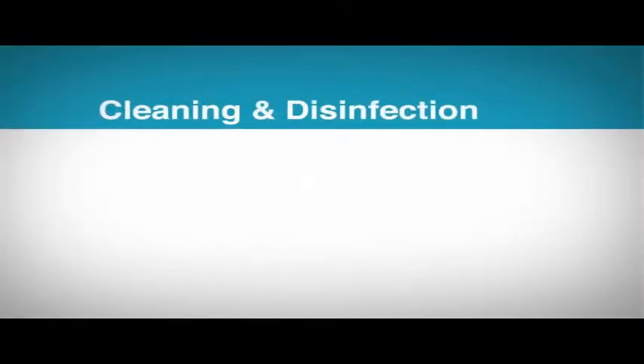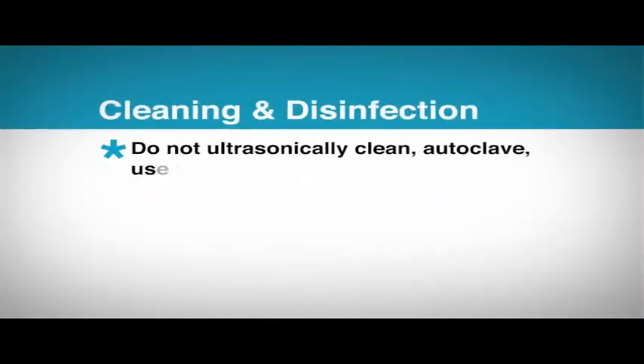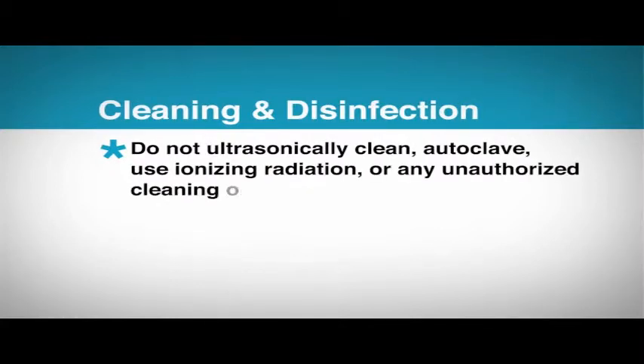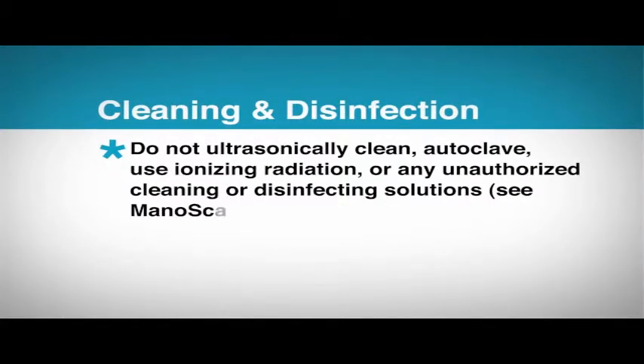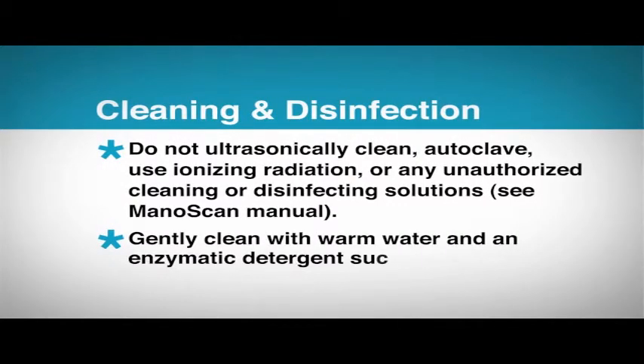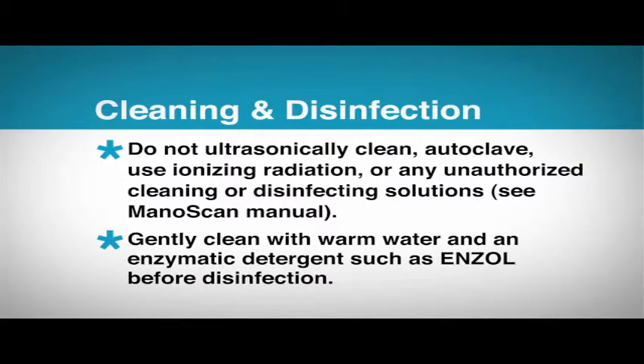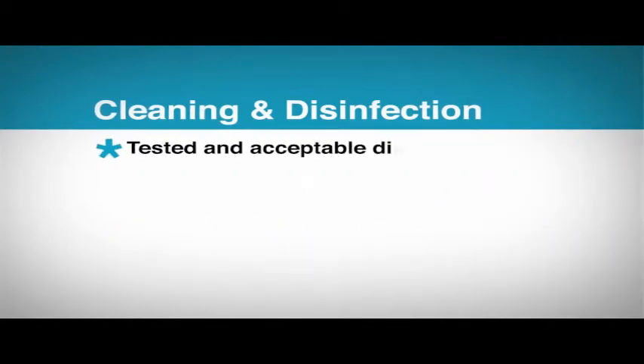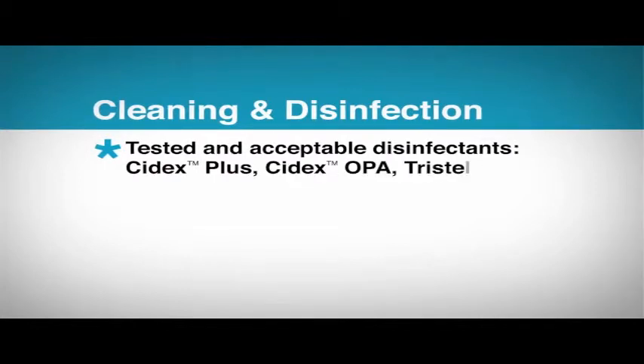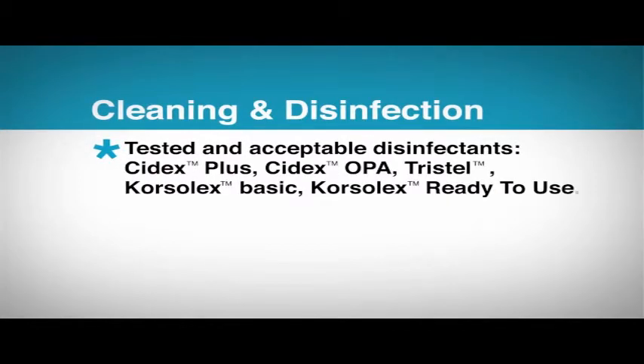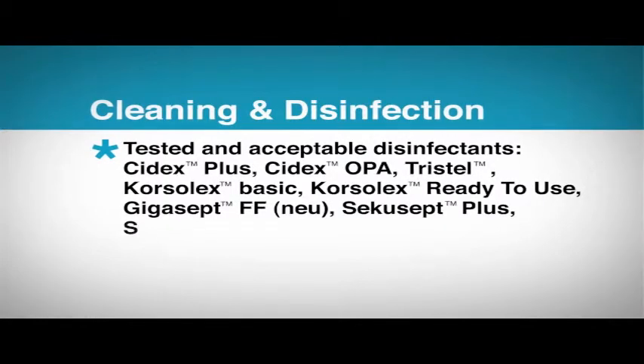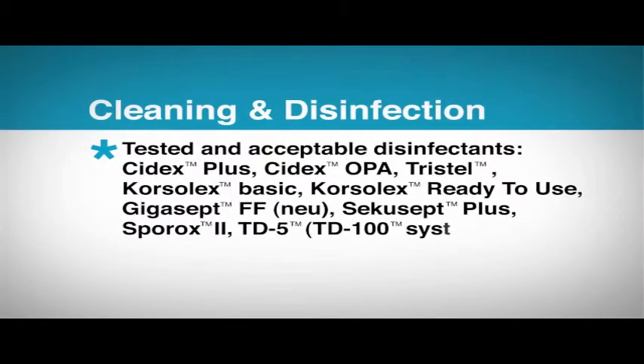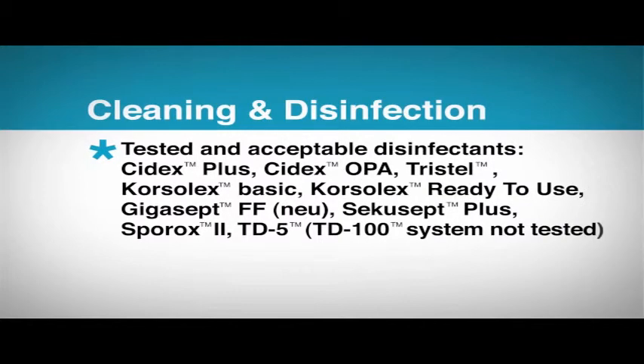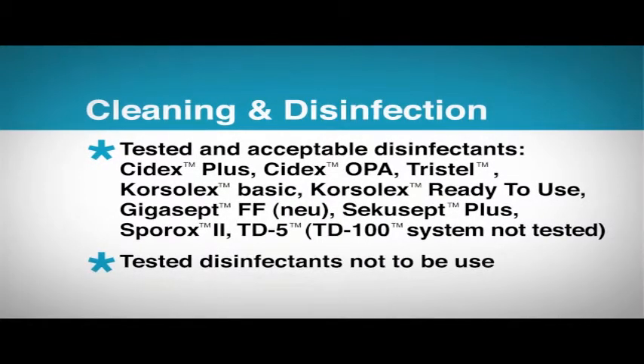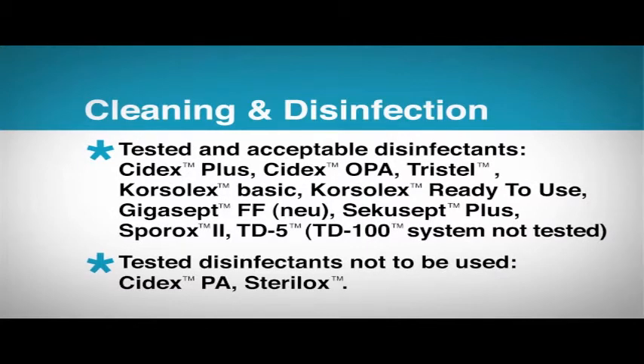Cleaning and disinfection. Do not ultrasonically clean, autoclave, use ionizing radiation, or any unauthorized cleaning or disinfecting solutions. See Manoscan manual. Gently clean with warm water and an enzymatic detergent such as Enzol before disinfection. Tested and acceptable disinfectants: Cidex Plus, Cidex OPA, Tristel, Korsolex Basic, Korsolex Ready to Use, Gigasept FF, Sekusept Plus, Sporox II, TD-5. Tested disinfectants not to be used: Cidex PA, Sterilox.